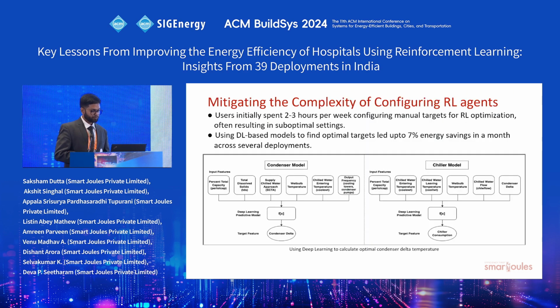The second challenge was optimizing the target settings. As we talked about, the PID or the rule-based engines required a lot of manual intervention. With the RL, asking users to put in the targets for any of the equipment was a tedious task. They required 2 to 3 hours per week, and scaling to 40 sites would require a lot of manpower just to put in an optimal target for an RL. But they were using design data and the environment condition, which was not feasible at scale.